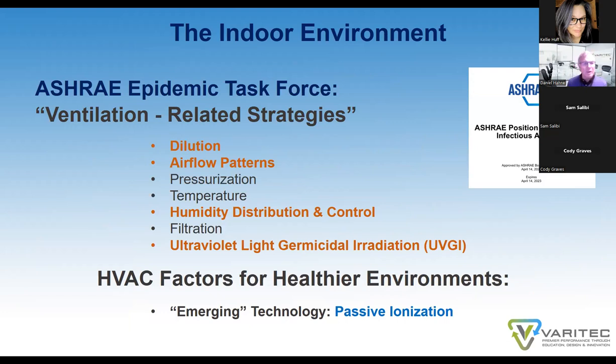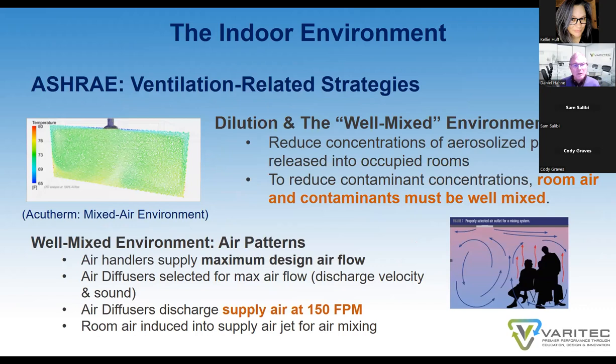Again, going back, let's look at ASHRAE's Epidemic Task Force, and that's ventilation-related strategies. We're going to look at dilution. We're going to look at airflow patterns. We're going to look at humidity distribution and control. And then we're going to look at ultraviolet germicidal radiation. And again, it's going to be a general flyover on these. I have one-hour presentations built on each of these sessions independently that we can provide at a future time. I'm also going to touch on an emerging technology acknowledged by ASHRAE of passive ionization. So let's look at ventilation strategy, dilution. Let's look at dilution and the well-mixed environment.